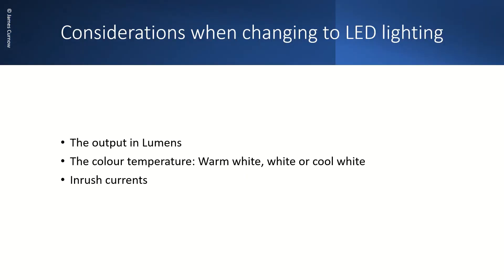Before changing to LED lighting, there are some considerations that we need to take into account. Firstly, the lighting output in lumens. Secondly, the colour temperature for the lamps, such as warm white, white, or cool white — I would suggest warm white for a home and white or cool white for commercial installations. Also bear in mind that LED lighting can produce inrush currents which can be accumulative, so even though the LED lamps use less energy overall, it is necessary to install enough circuits to ensure that inrush currents don't cause unwanted tripping.